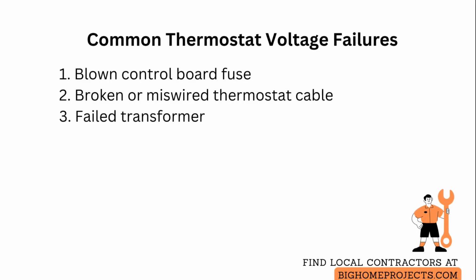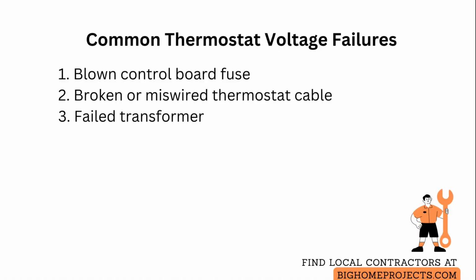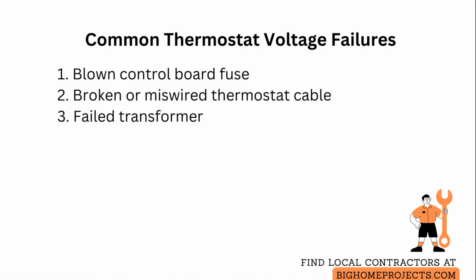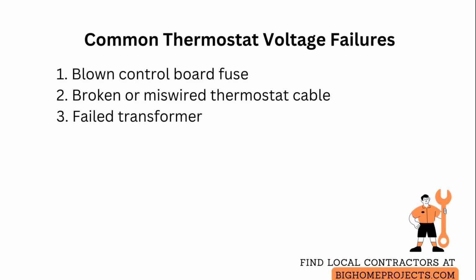The 3 most common issues are a blown control board fuse, broken or miswired thermostat cable, and a failed transformer. Replace a blown fuse with the correct rated fuse and investigate what caused the blow before leaving it replaced.